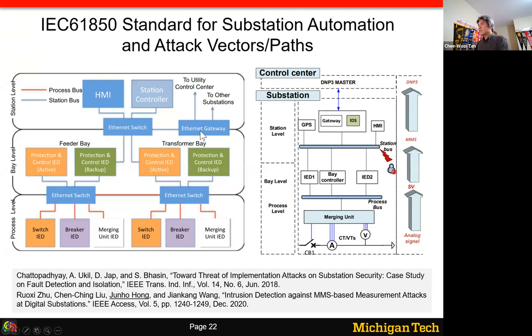Communication between the control center and substations is also enabled these days. What you see here is a standard communication protocol called IEC 61850. The reason we need a standard is for interoperability. For example, one company is a major manufacturer of substation relays, but we could also have other vendors out there. For them to communicate easily, a standard has to be established. Otherwise, you'd have to buy a device from one vendor and then you couldn't find a second vendor to fix the issue, because of proprietary communication information.